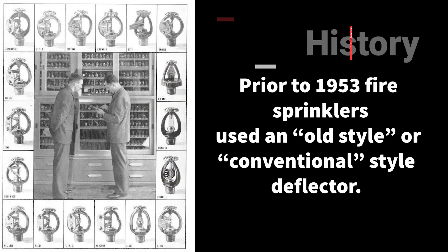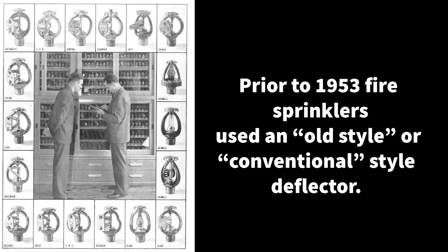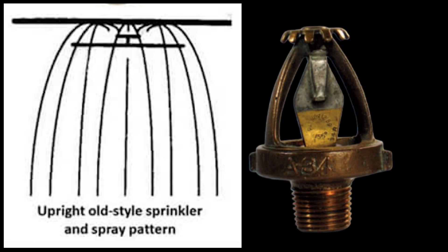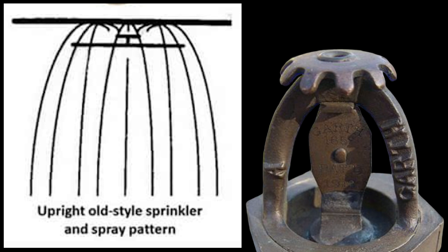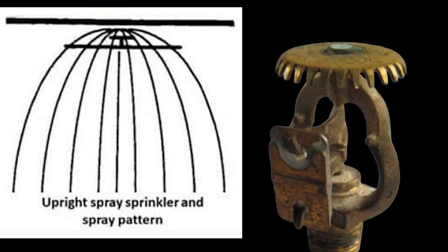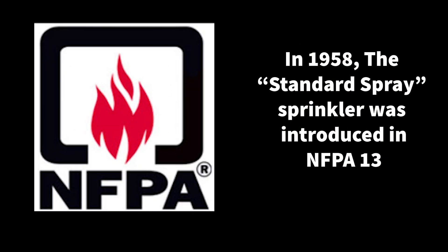Prior to 1953, sprinkler heads used an old style or conventional style deflector. Its spray pattern would throw up to 60 percent of its discharged water upwards, creating a very vertical spray pattern. In the early 1950s there was an improved deflector that created the umbrella shaped spray pattern we know today, achieving a larger square footage of coverage. In 1958, NFPA 13 introduced the standard spray sprinkler, which became the most commonly used fire sprinkler head.